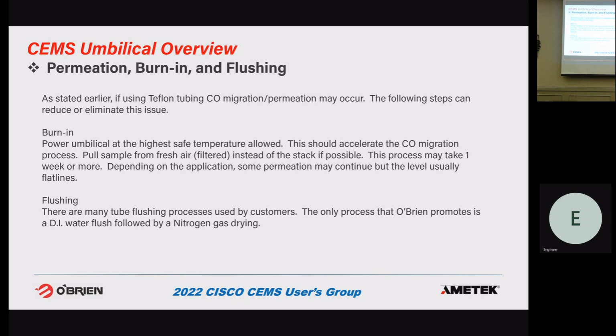I don't know. So in general there should be a point where the CO stops migrating, because it's coming from the thermal insulation. All the major tubing bundle manufacturers use the same two insulation manufacturers, and there's a binder holding those fiberglass fibers together. It's that binder burning off at higher temperatures, near 400F, and once those binders are burned off, the CO should stop.